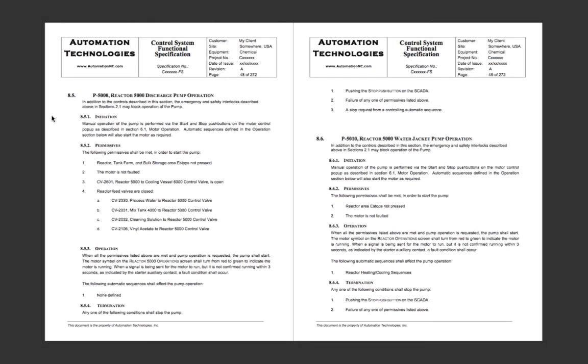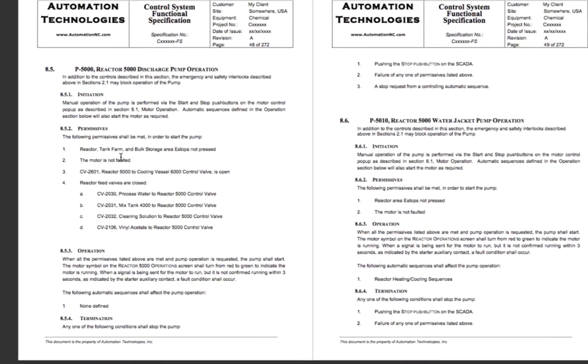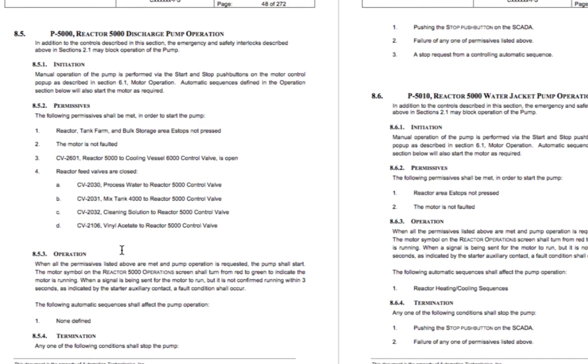Let's look at some of the sections we have here. You can see we have several subsections within the description of this particular pump. We have how it initiates — what gets it started — what the permissives are. These are the things that are required to be okay before our pump can run. And then how it's going to operate, and then termination — what stops it. This is a lot of information, but it allows everybody to understand exactly how this particular piece of equipment is going to work.